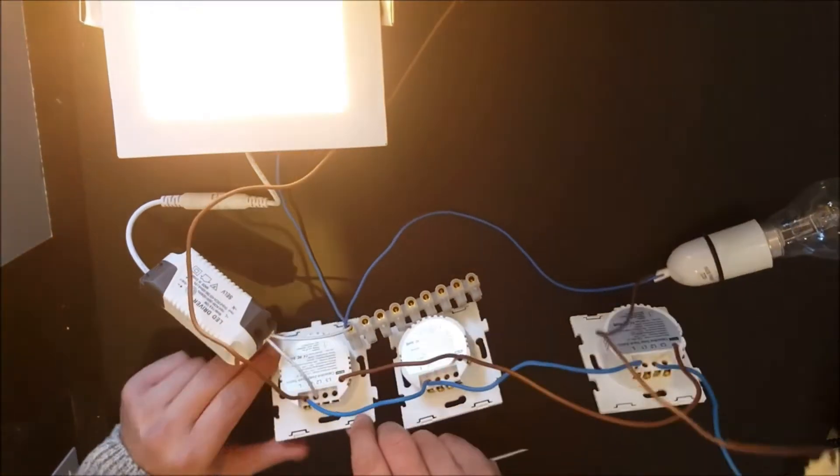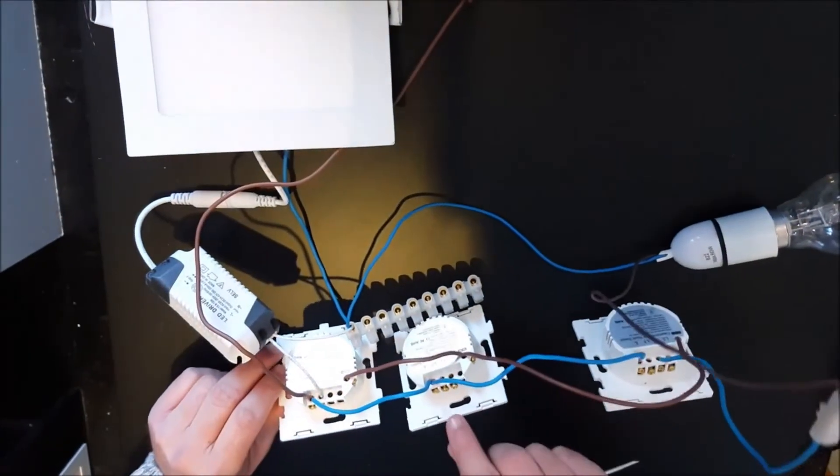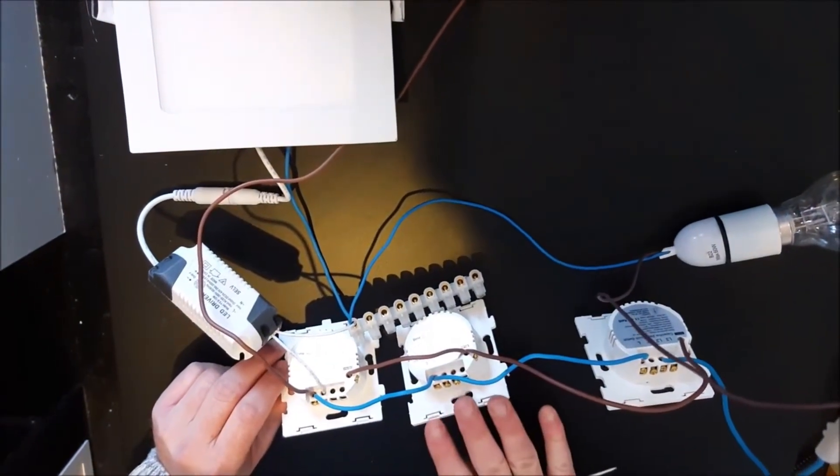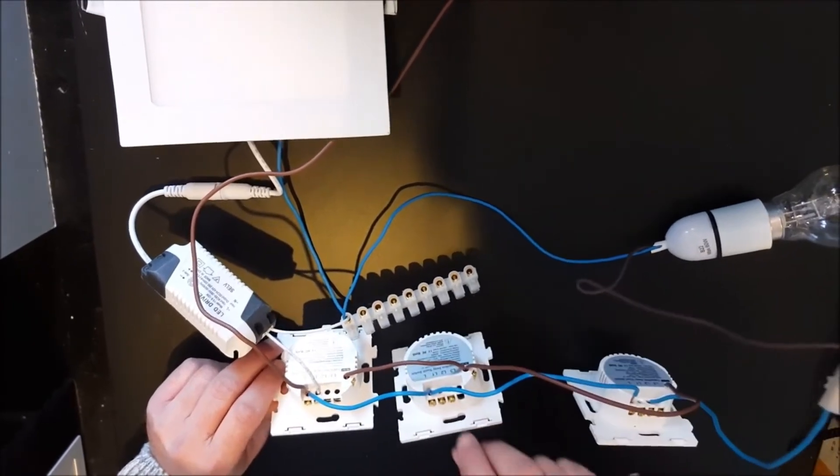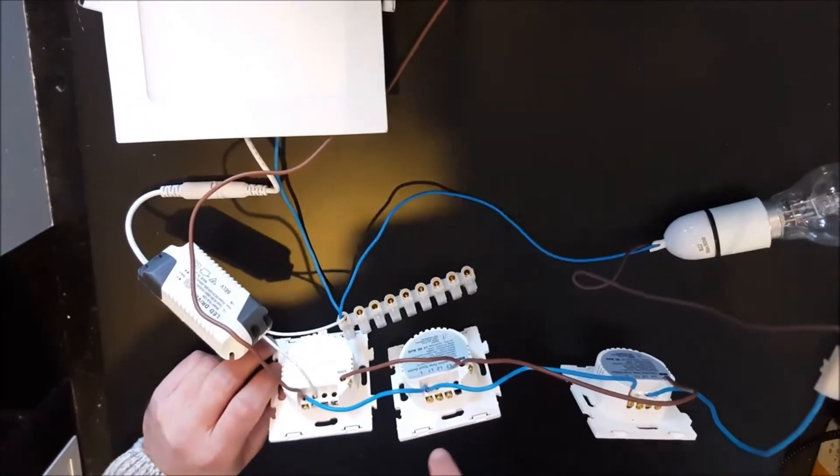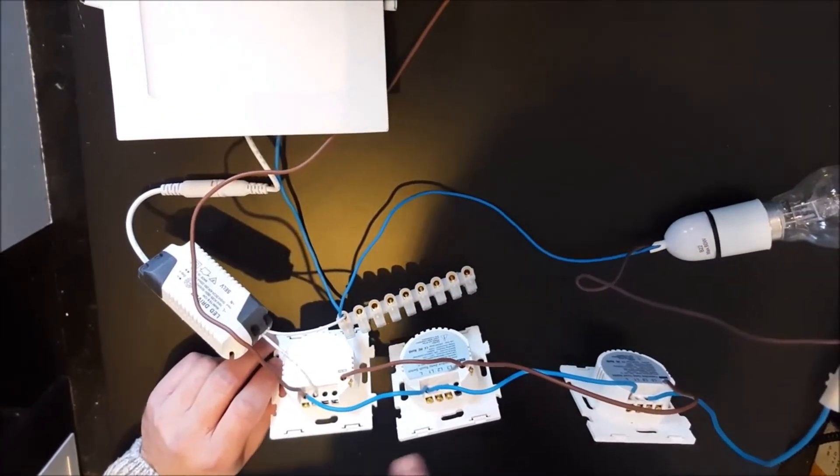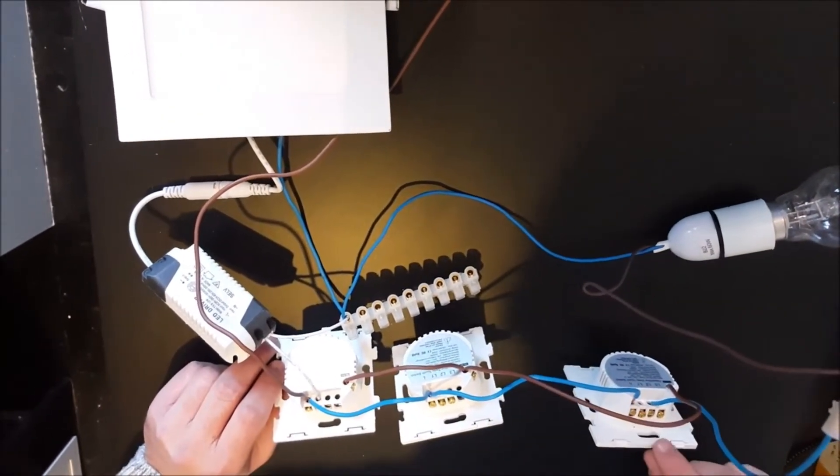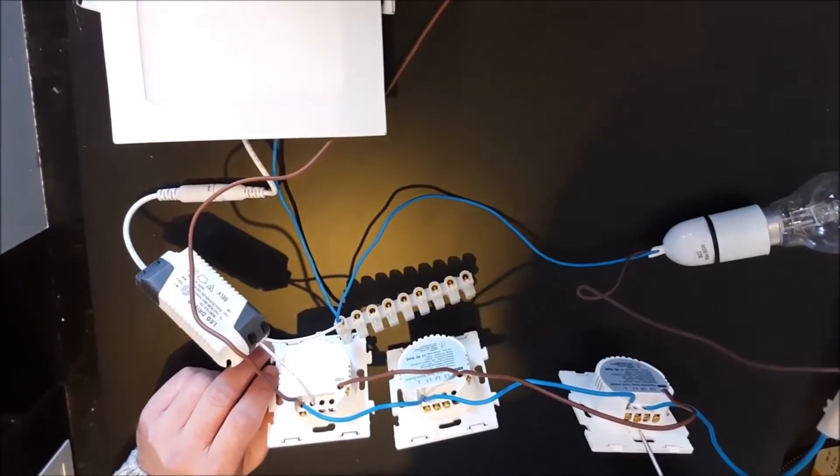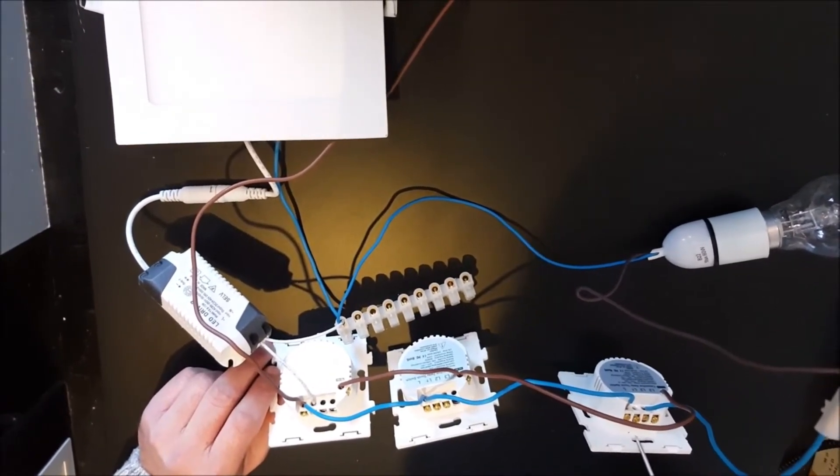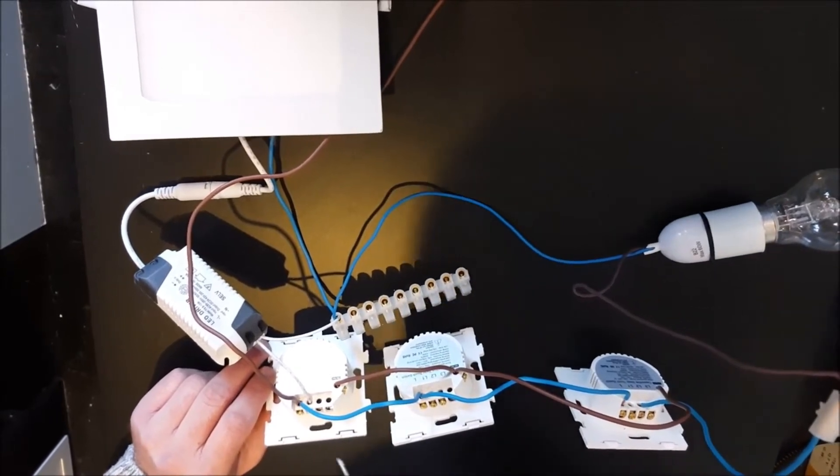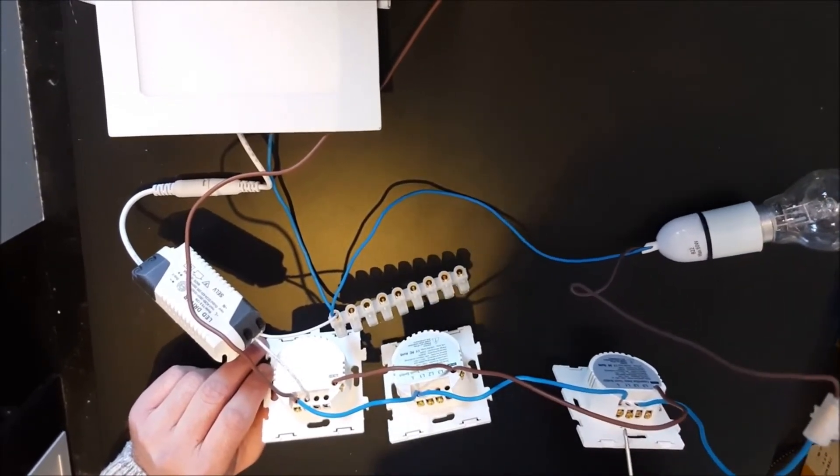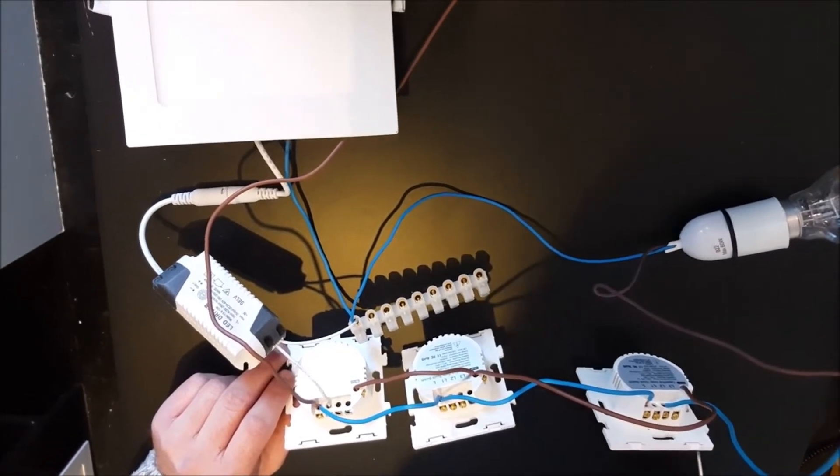I have another one, no I have no switch lives in here. This is left empty because this will be an intermediary switch which is going to have one of them working as a three-way, one of them working as a two-way. Over here I have the L1 terminal empty because that will also be used as a three-way because what happens is L1 of each switch will work together, L2 will work together, and L3 will work by itself because there is no corresponding L3 terminals.